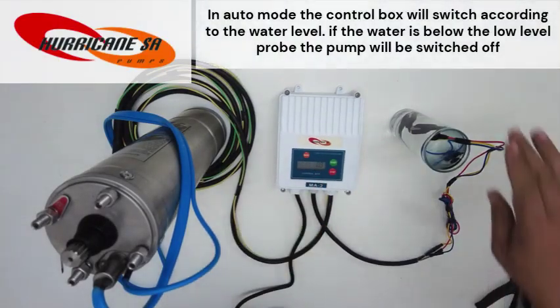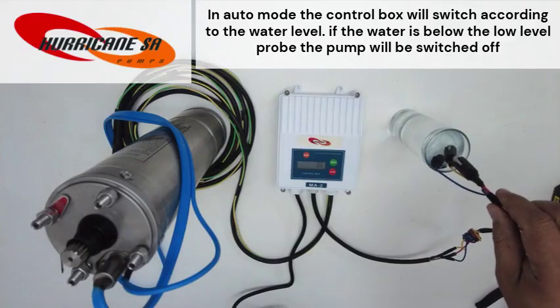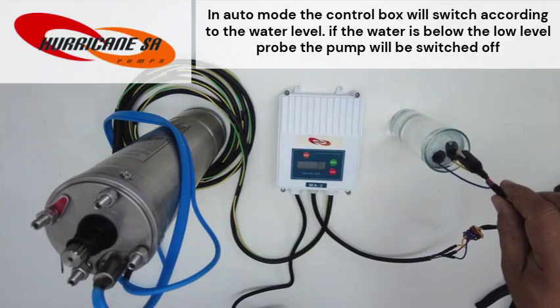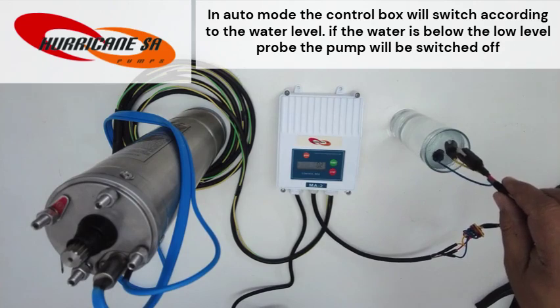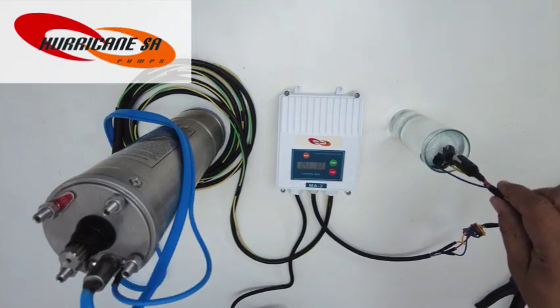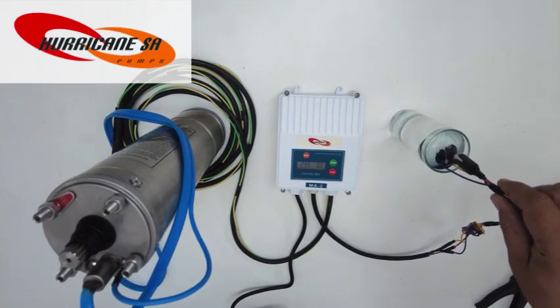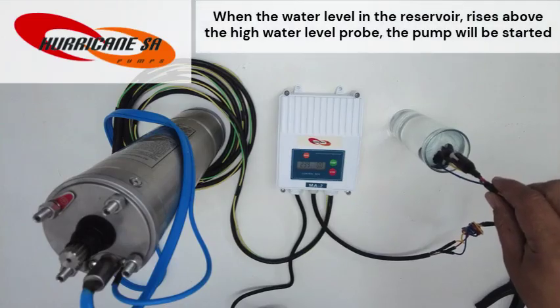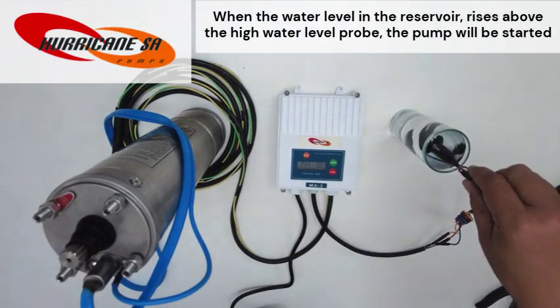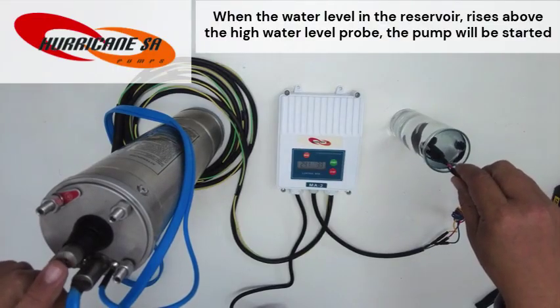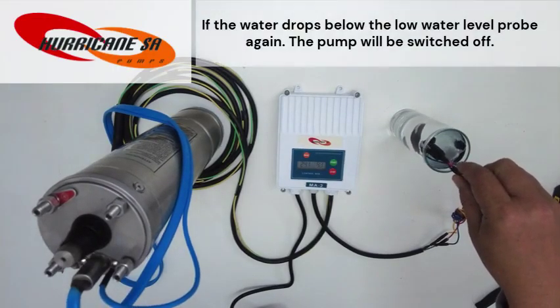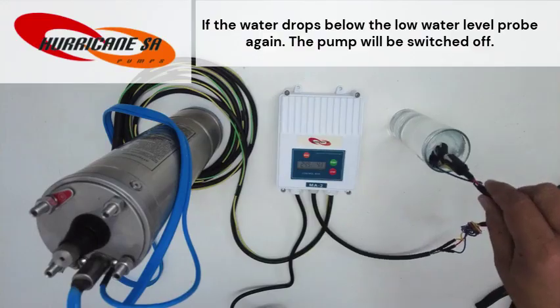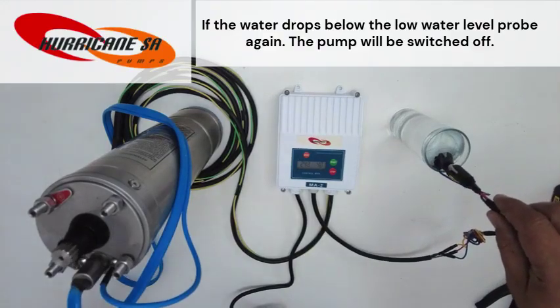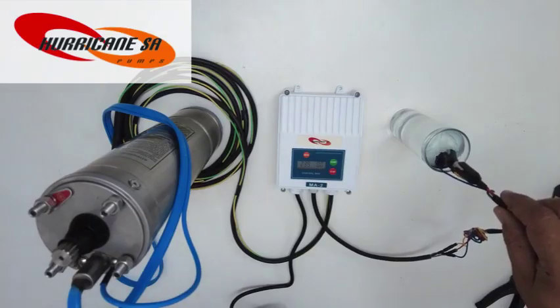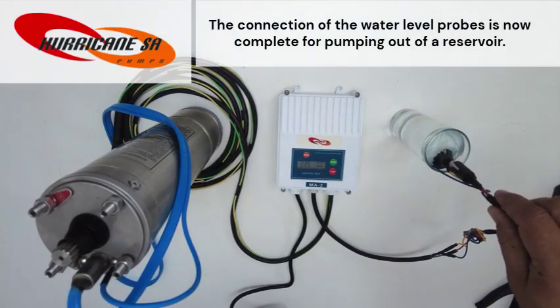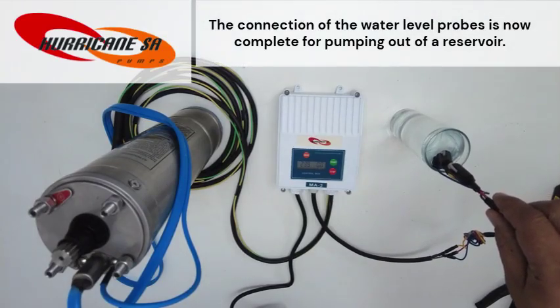In auto mode, the control box will switch according to the water level. If the water is below the low level probe, the pump will be switched off. When the water level in the reservoir rises above the high water level probe, the pump will be started. If the water drops below the low water level probe again, the pump will be switched off. The connection of the water level probes is now complete for pumping out of a reservoir.